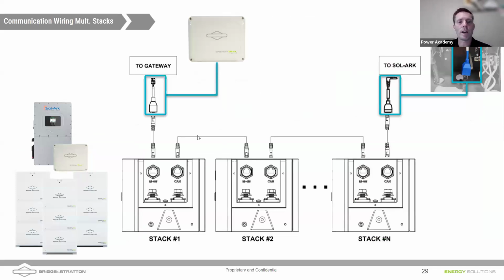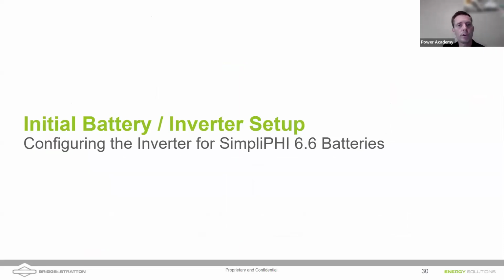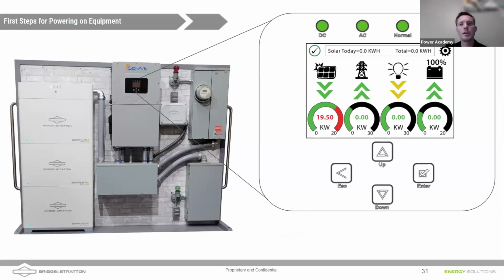You daisy chain the batteries, you connect the CAN bus output of the first stack to the second stack to the third stack, and then that third stack CAN bus battery channel is going to be running into the Sol-Ark. That's what allows the batteries to dictate to the Sol-Ark how fast they wish to be charged, what their voltage is, and all the other information that runs on that CAN bus channel. It's fairly simple in terms of the wiring.